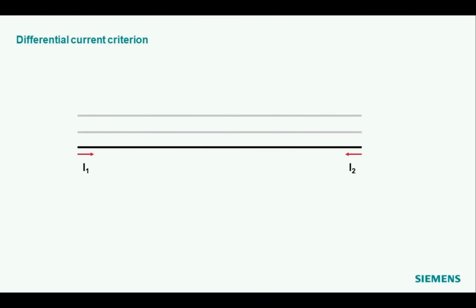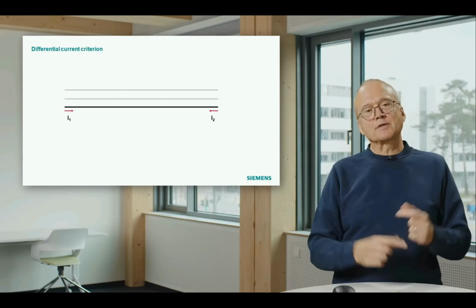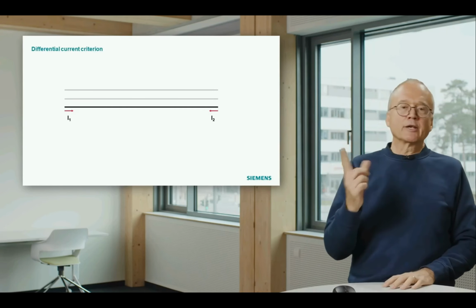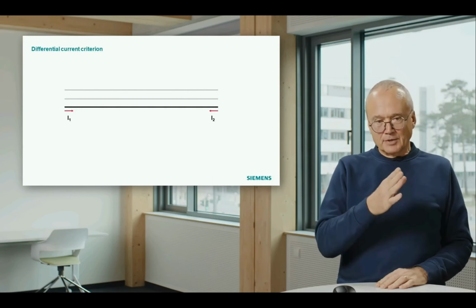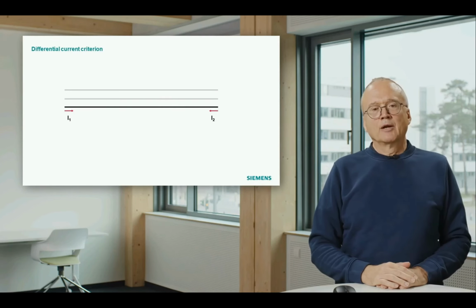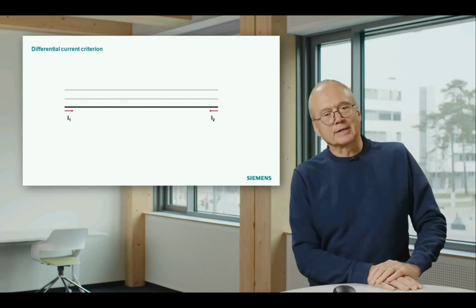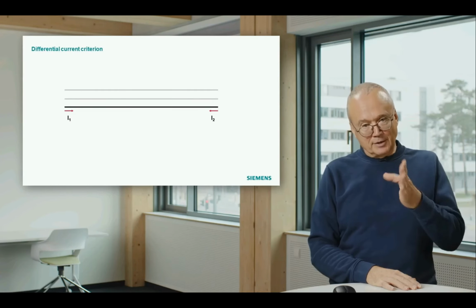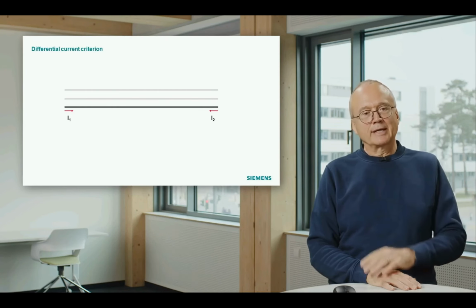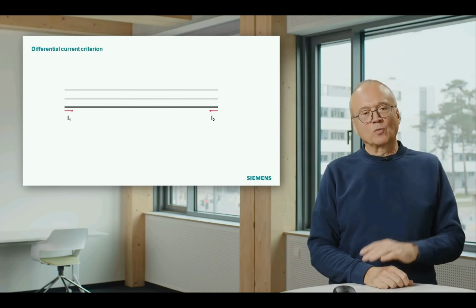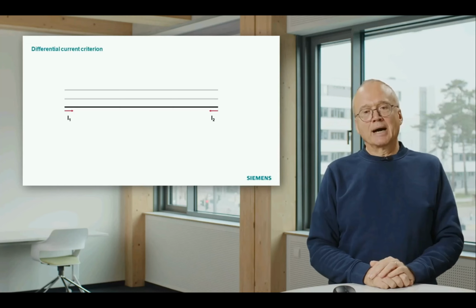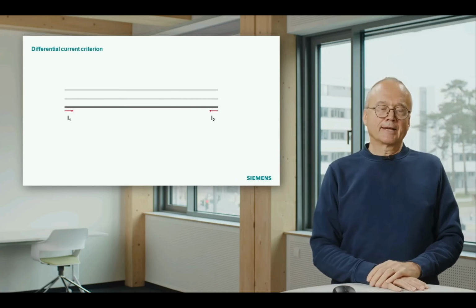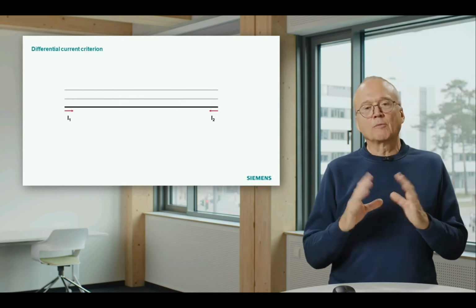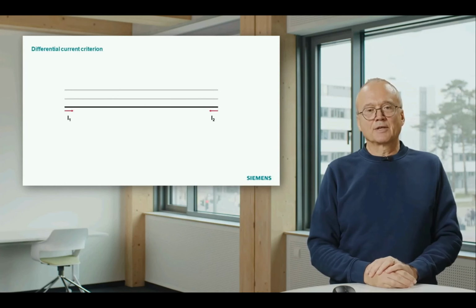Third criterion was the differential protection. What is the idea there? Remember, you have a simple line. I indicate here the three phases. I first of all focus just on one phase. You measure the current at both ends of the line, in this case indicated as I1 and I2. Normally, current flowing into the line is calculated as positive. That means if we have in this picture here a current flow from left to right, let's assume 100 amps, I1 would be 100 amps and I2 would be minus 100 amps because it flows against the indicated direction. That means in normal operating state, the sum of these two currents is 0.